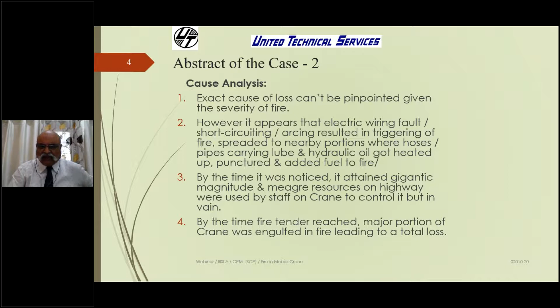What happens over a period of time? These cables are tied normally, tied with various tags, various brackets. But over a period of time, because of vibration and abrasion with the metal part, the insulation gets chafed, gets cut, and at some point of time conductor comes in touch with the body, and heavy current is drawn, which initiates heat, and the insulation catches fire, which results into this fire.